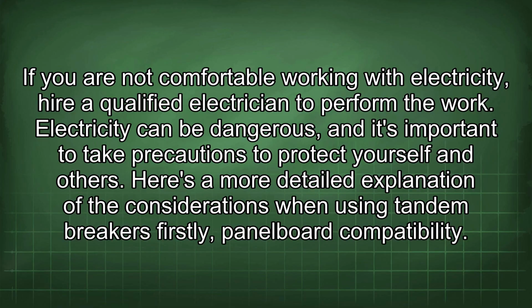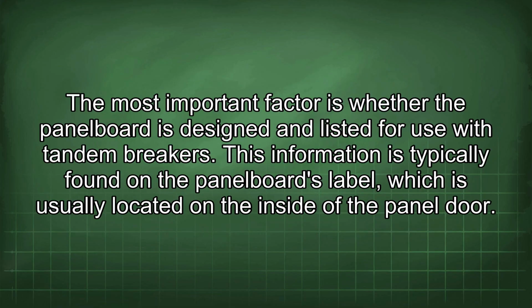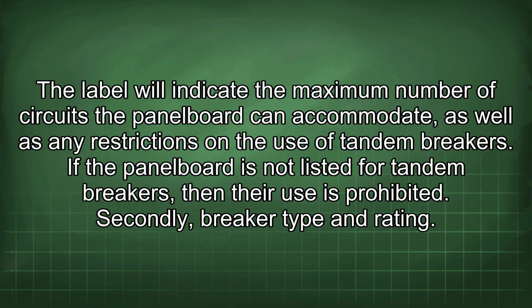Here's a more detailed explanation of the considerations when using tandem breakers. Firstly, panel board compatibility. The most important factor is whether the panel board is designed and listed for use with tandem breakers. This information is typically found in the panel board's label, which is usually located on the inside of the panel door. The label will indicate the maximum number of circuits the panel board can accommodate, as well as any restrictions on the use of tandem breakers. If the panel board is not listed for tandem breakers, then their use is prohibited.